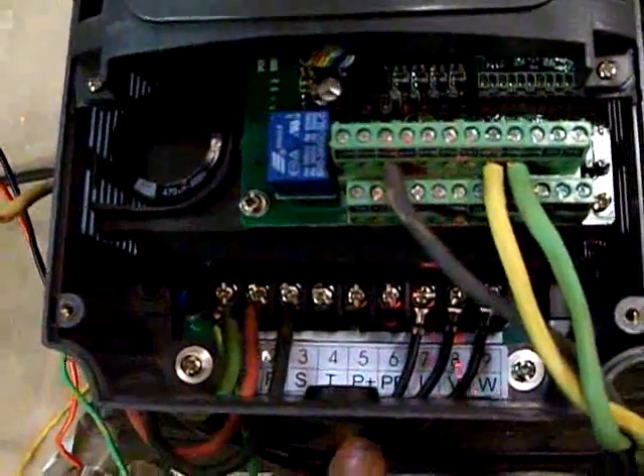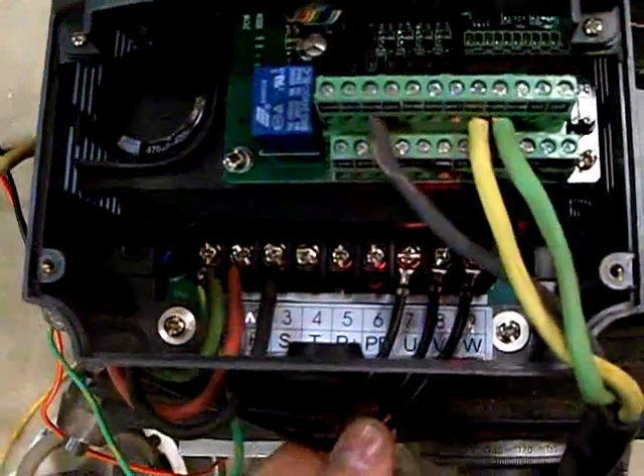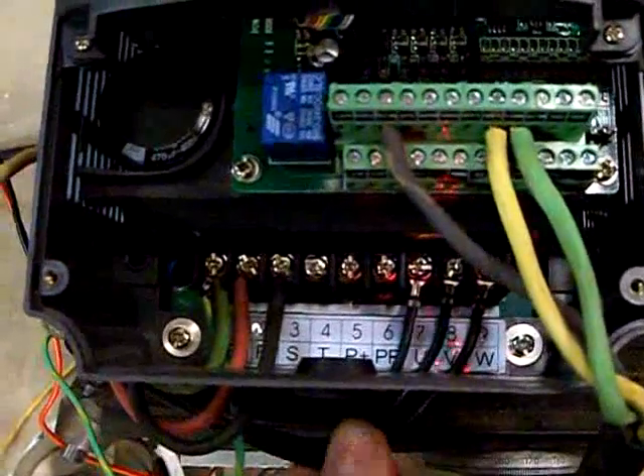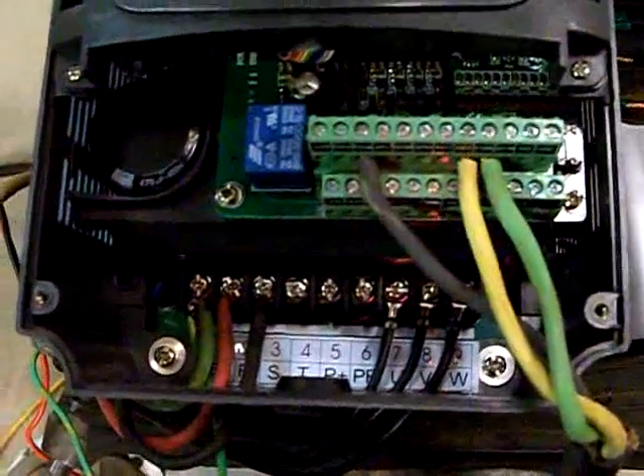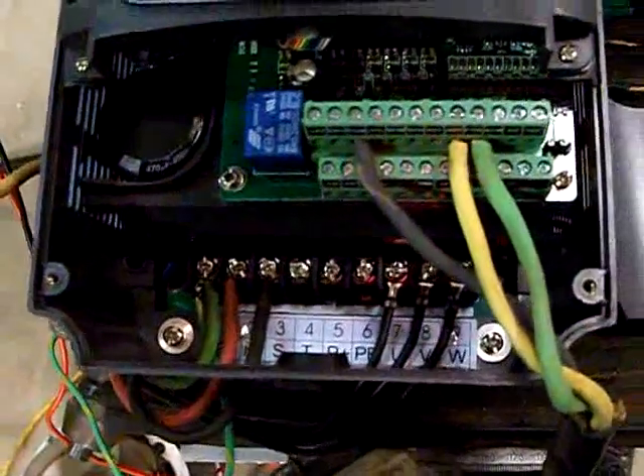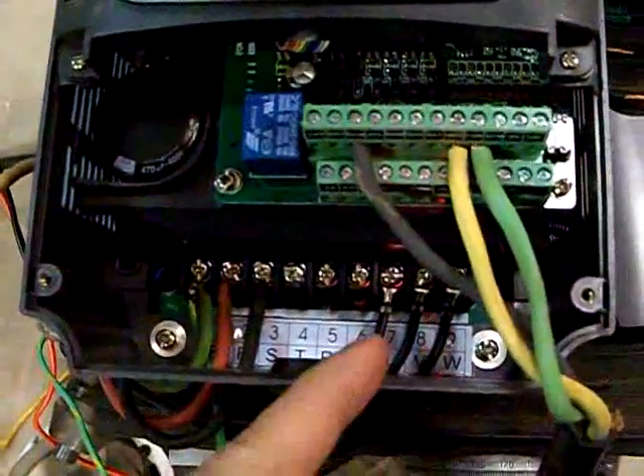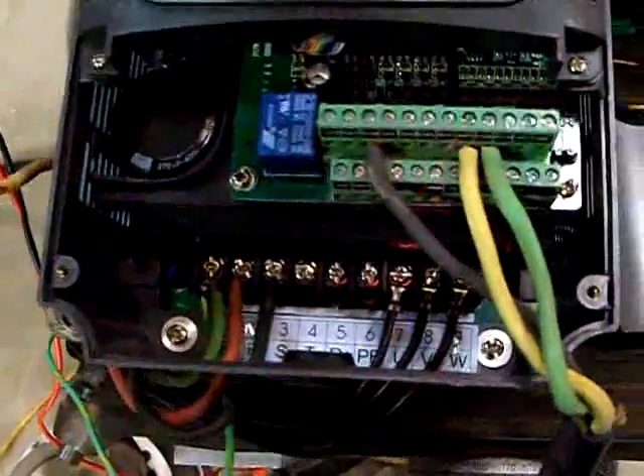The U, V, and W, that's your three-phase to the motor. Doesn't matter which way you hook that up at first. If you realize that the rotations are going the wrong way, you can flip any two wires and it'll reverse the rotation.